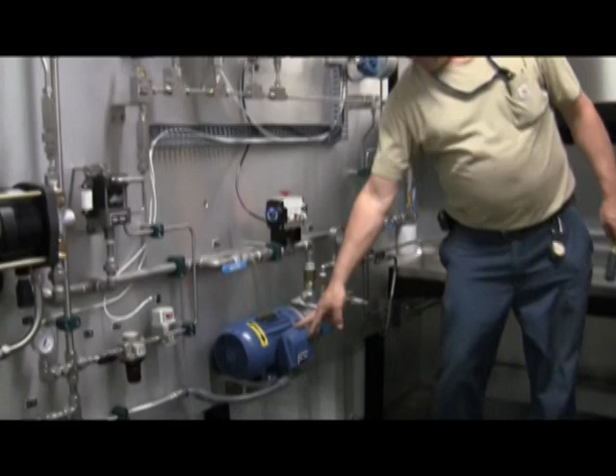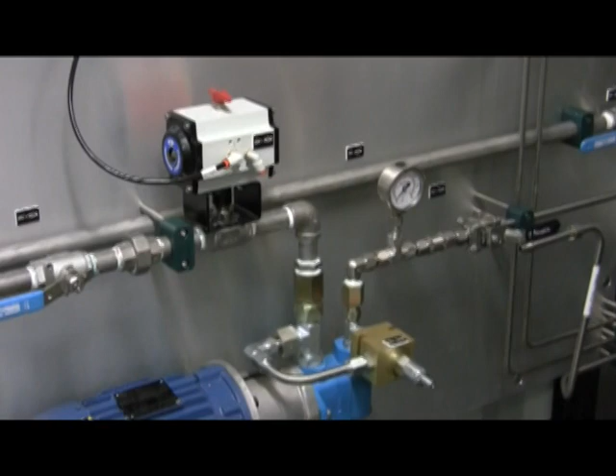John, let's start at the fast fill pump. Alright, there's your fast fill pump, same as what we had on the previous FAT. There's the inlet valve to the pump, and there's the bypass valve, set at about 350 PSI. So your fast fill system can get up to anywhere from 250 to 350.